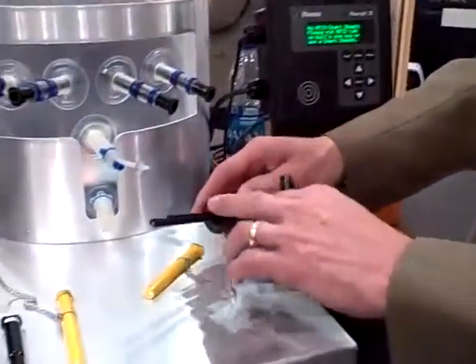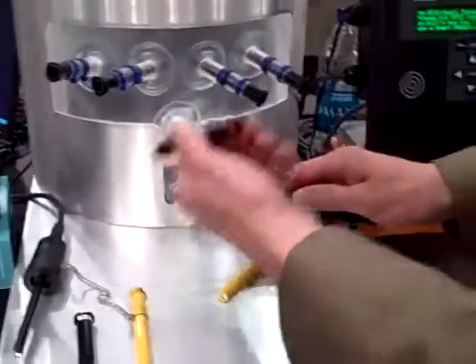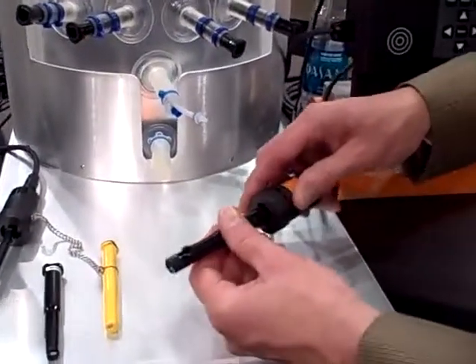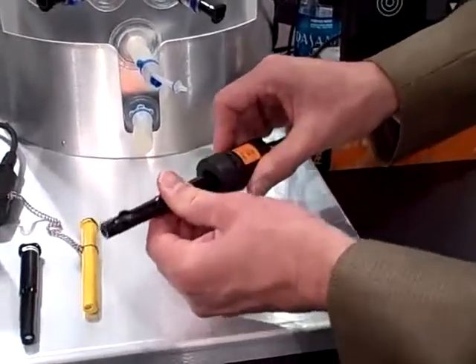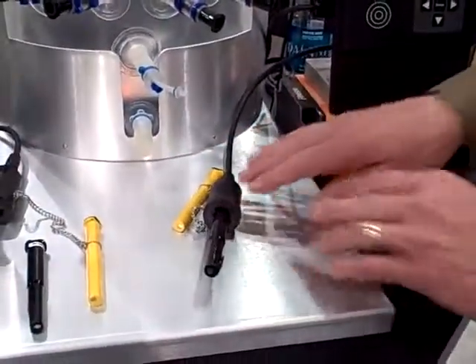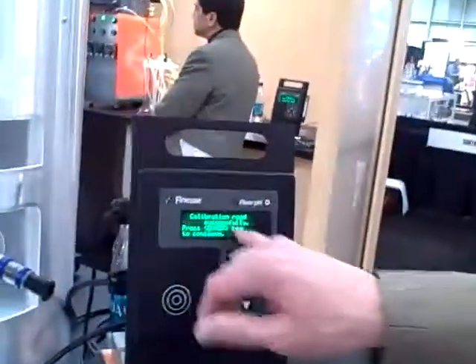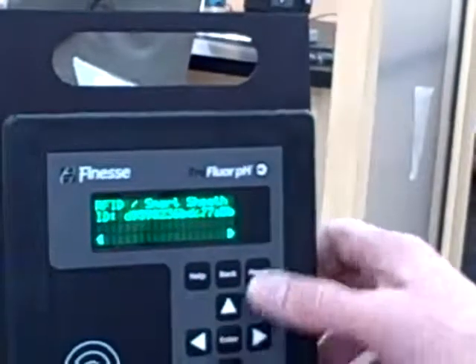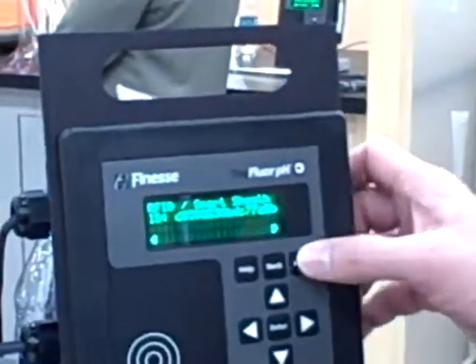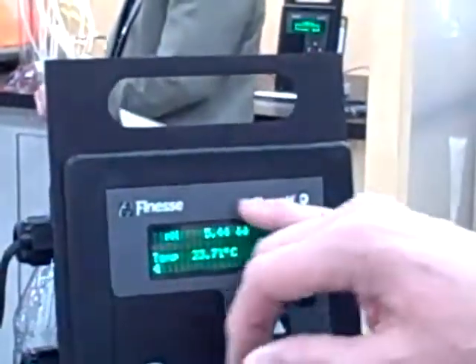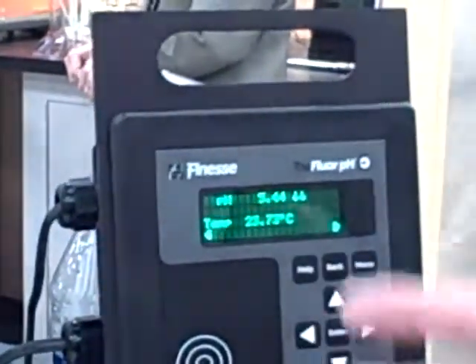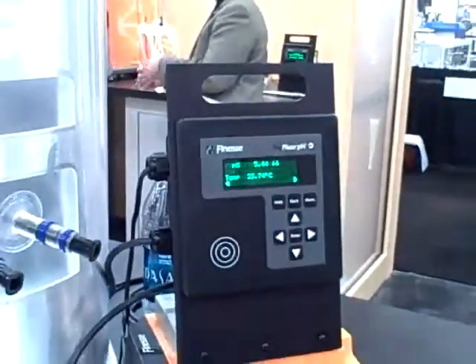So what happens is you use this keyed reader and match it up to the sheath, which, like I said, is going to be in the bag. You just slide it in, lock it, make sure it's locked, and the reader and the transmitter work together and read the calibration. This says calibration read successfully. Press enter, and it gives you the information you need for traceability. You can press menu twice and it comes out, and you can read the pH and the temperature, two process variables at the same time.